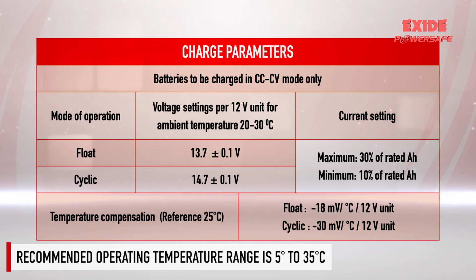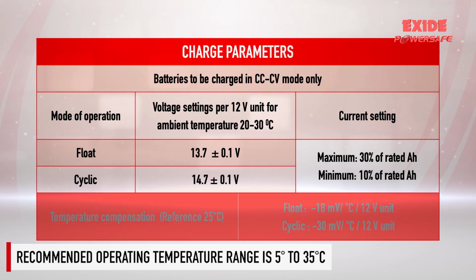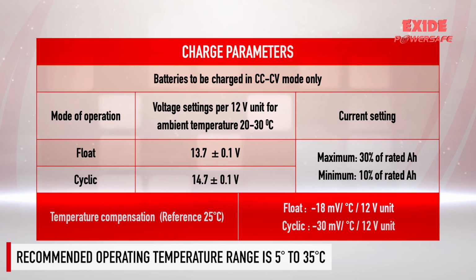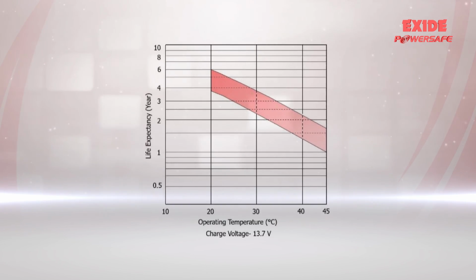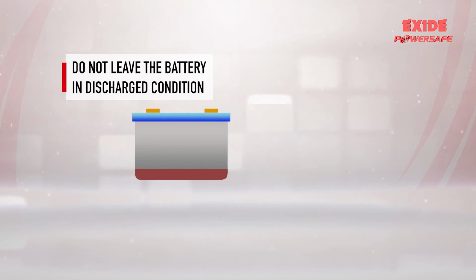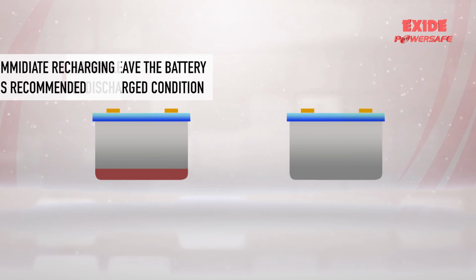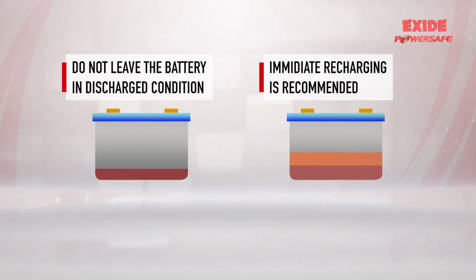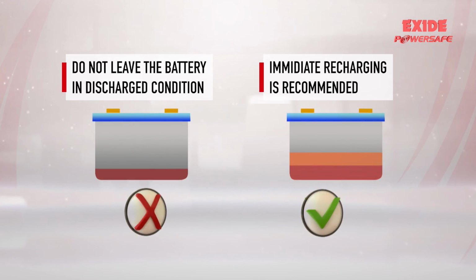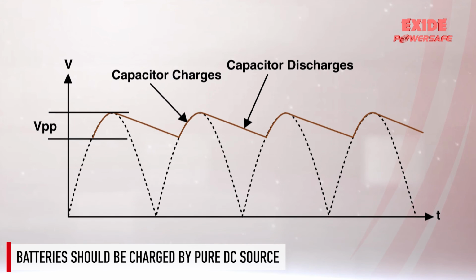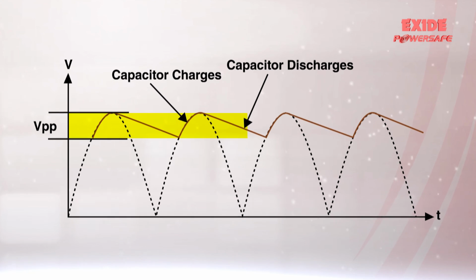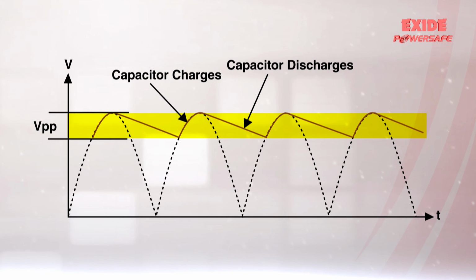Operating the battery at an ambient temperature of 5 to 35 degrees Celsius is recommended to prevent any adverse effect on its effective life. The battery life will be shortened as operating temperature rises. The battery should never be left in a discharged condition, otherwise the battery's full capacity may not be recovered. Immediate recharging is recommended. VRLA batteries should be charged by pure DC source only. The ripple voltage of the charger shall be less than 0.5% peak to peak of the set battery string voltage.